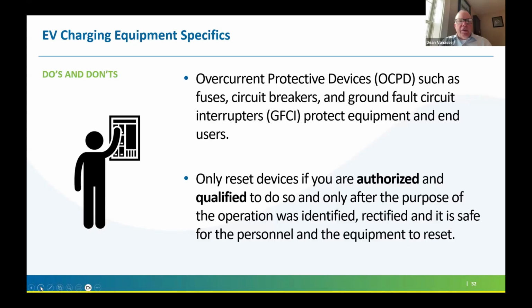Some EV charging equipment specific do's and don'ts: overcurrent protective devices. These are fuses, circuit breakers, maybe the line side supply of a charger could even have a ground fault circuit interrupter for the AC component. These devices operate for a reason, either an overload condition or a fault condition, and we need to understand why that device operated before we go ahead and reset it.